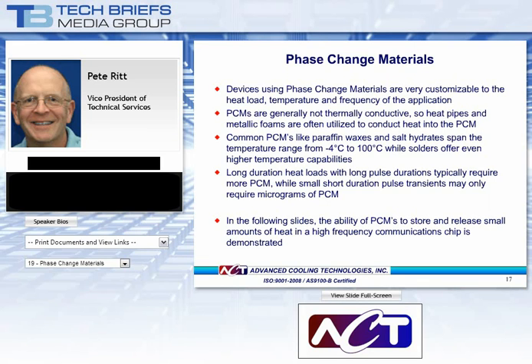Let's talk a little more about PCMs. Devices using phase change materials are very customizable to the heat load, temperatures, and frequency of the application. PCMs are generally not thermally conductive, so heat pipes and metallic foams are often utilized to conduct heat into the PCM. Common PCMs like paraffin waxes and the salt hydrates span the temperature range from -4 to 100 degrees C, and with solder, even higher temperatures can be achieved.